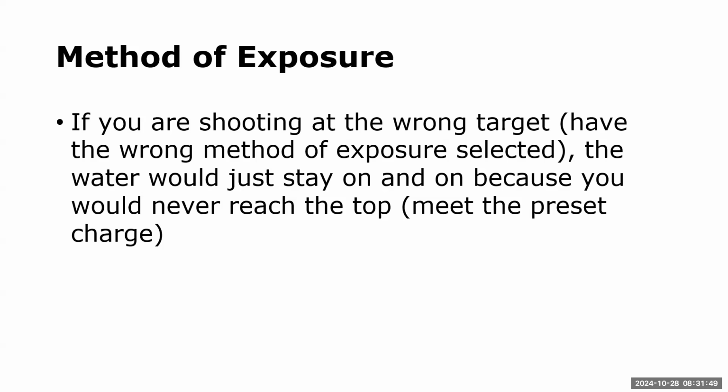But there's a lot of rooms out there that will still let you make these kinds of mistakes. So what this is saying is if you're shooting at the wrong target, in other words, if I have the wrong method of exposure selected, so let's say I'm doing an abdomen in the table bucky, but I have wall bucky selected.